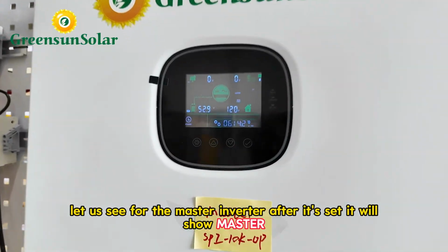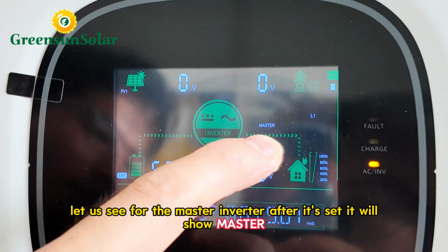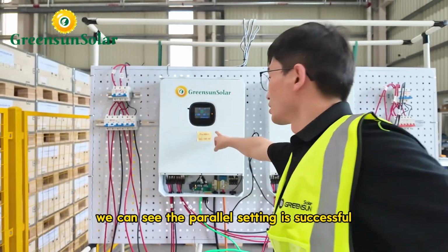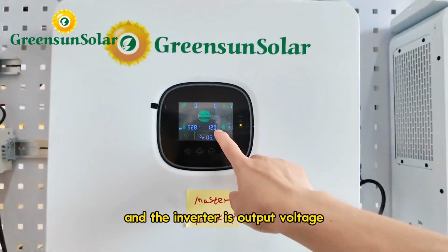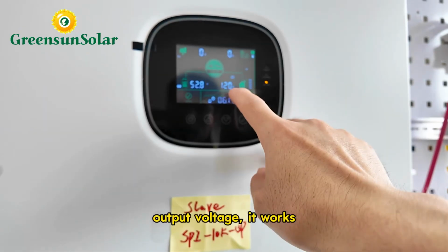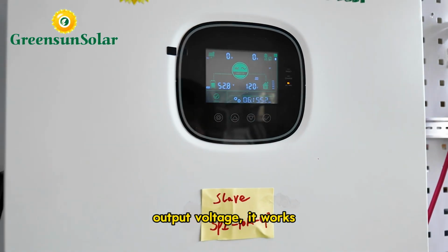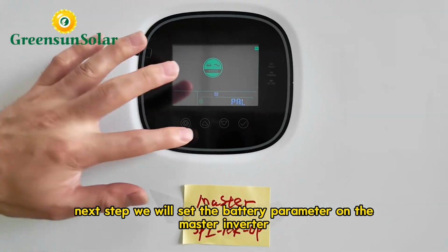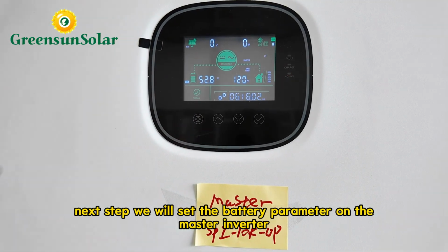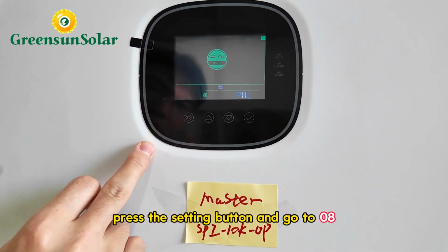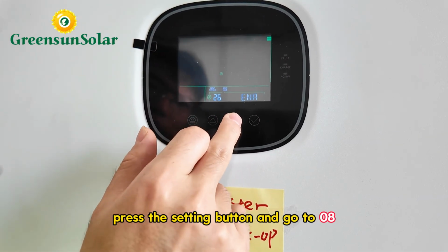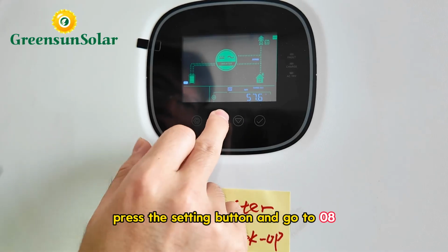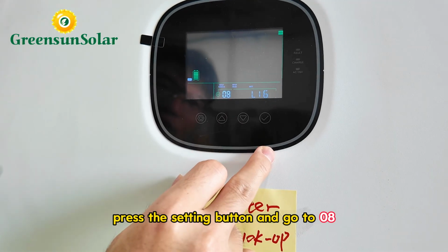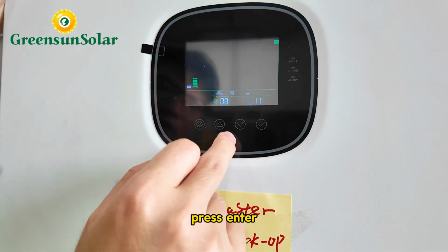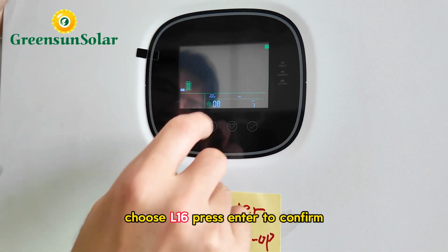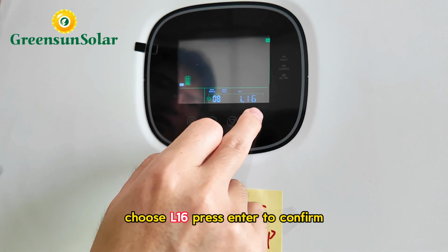Let us see the master inverter. After it is set, it will show master. We can see the parallel setting is successful, and the inverter has output voltage. It works. Next step, we will set the battery parameter on the master inverter. I press the setting button and go to 08. Press enter and choose L16. Press enter to confirm.